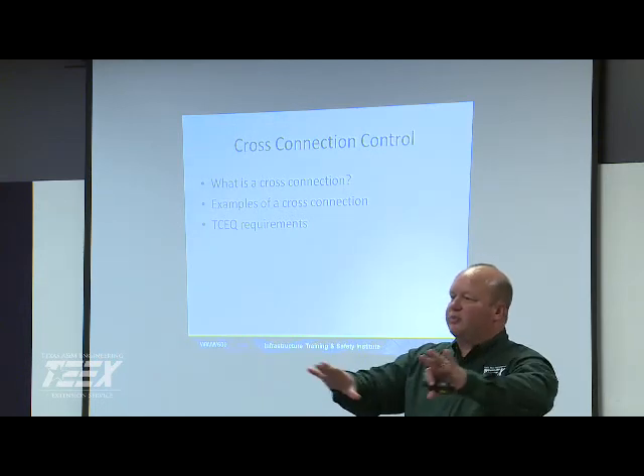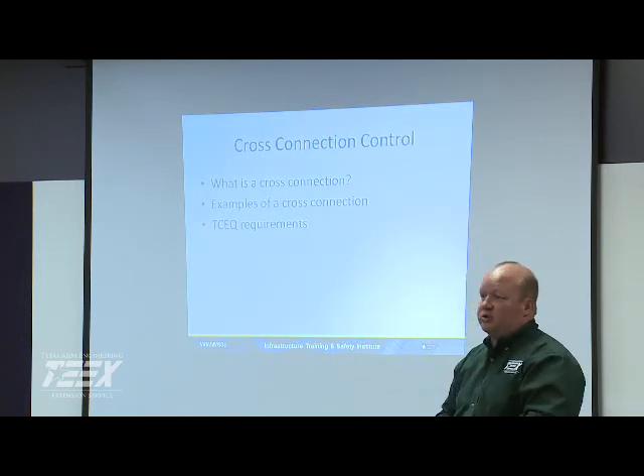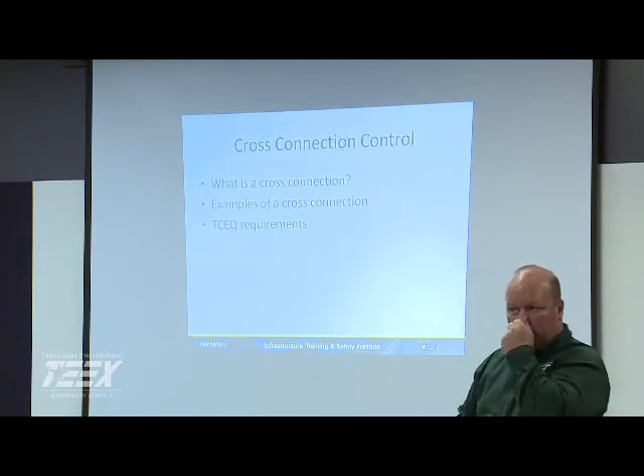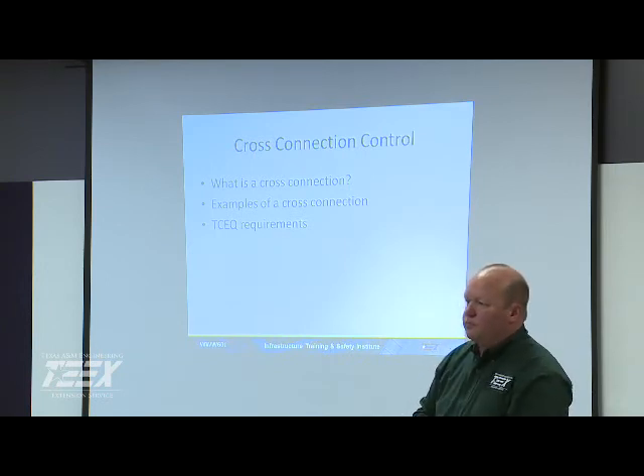Well, you got to keep your system separated. Yeah. That's your biggest thing, is getting into your cross connection controls. One of the things that came up was in the system here that wants to use it for the park. They wanted to use it for the toilets also, and once it got to the building, it was going to be all copper pipe. And so that's a concern for us, is if you've got copper pipe in there and it's not marked, you get a plumber in there that may not be paying attention, he cross-connects between the sinks, and that's a concern. Yeah, it's big color code.